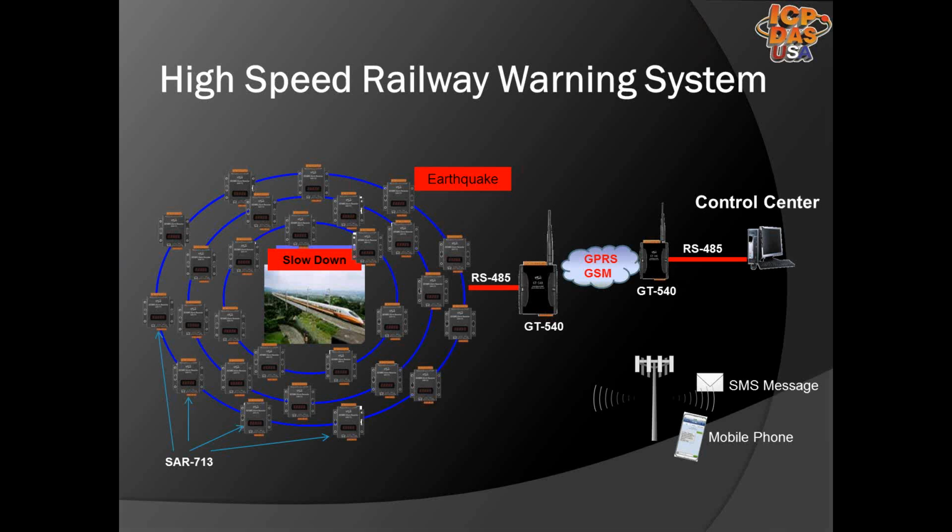The SAR 713 Modbus-based seismic recorders are attached to GT540 cellular-based Modbus device servers. The data gets passed back over the cellular network to a control center. SMS text messages are sent out to alert proper personnel.